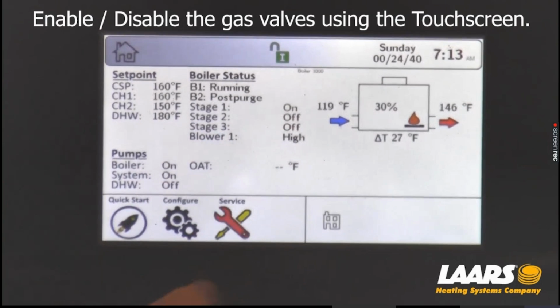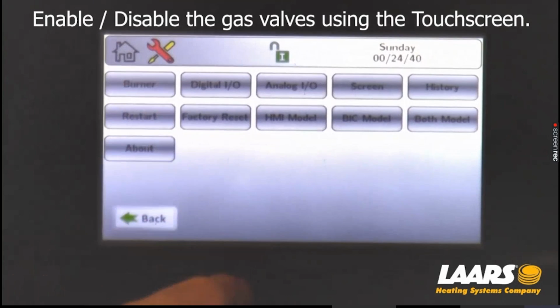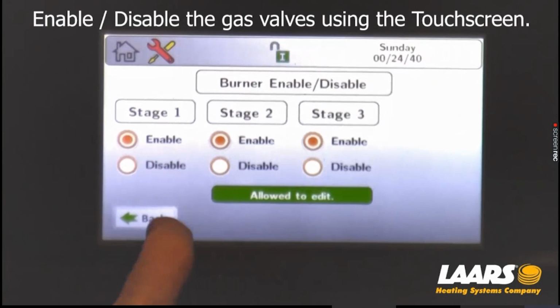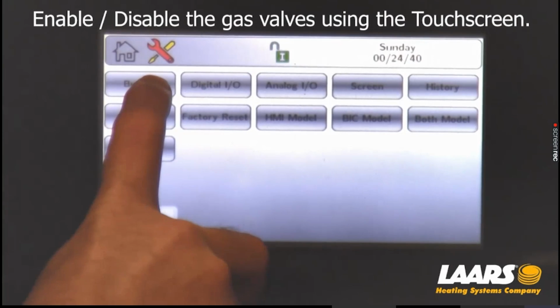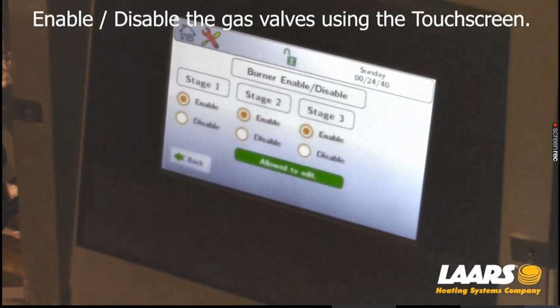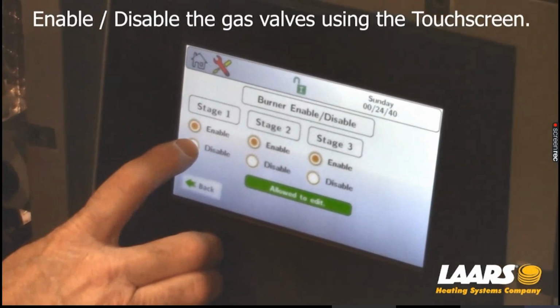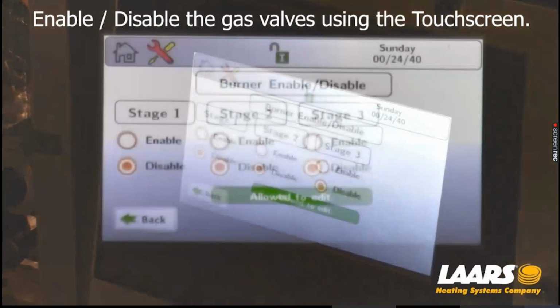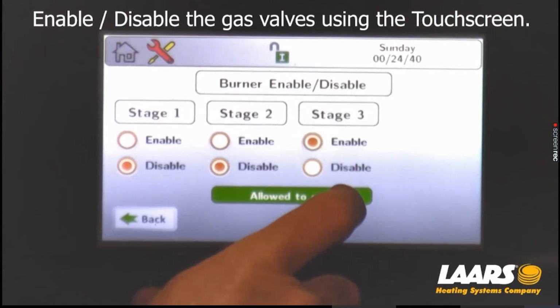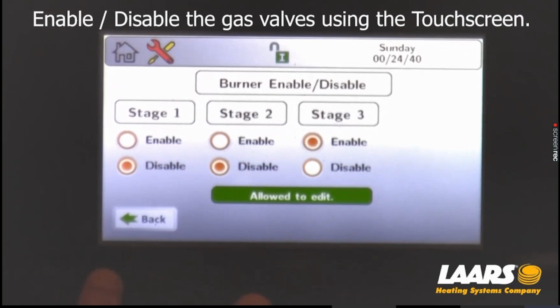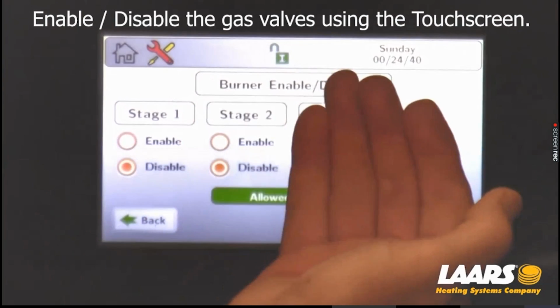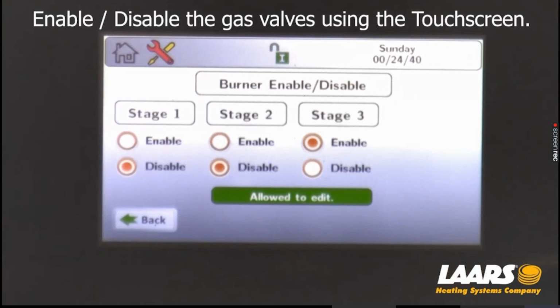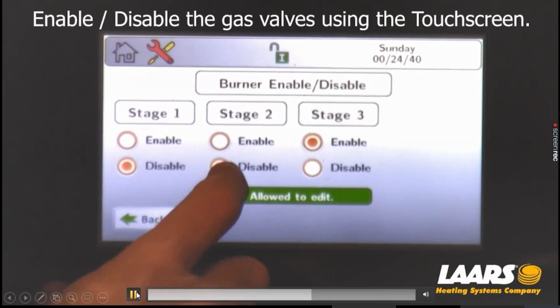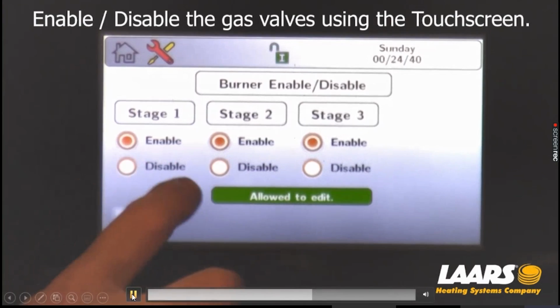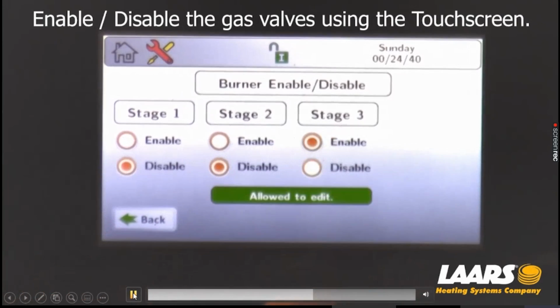However, I'm going to go back in here again, service, burner. I'll enable these stages for an example. And if you only have a single stage boiler and you choose to shut off valve 1, it automatically will shut the other valves off. Okay? You should be able to go in and with this it has 2 igniters. So if you've only got 1 igniter and you've got a 2-stage boiler, so only stage 1 and 2, the igniter is under stage 1. That's why when we tried to change it, it changed both stage 1 and 2.